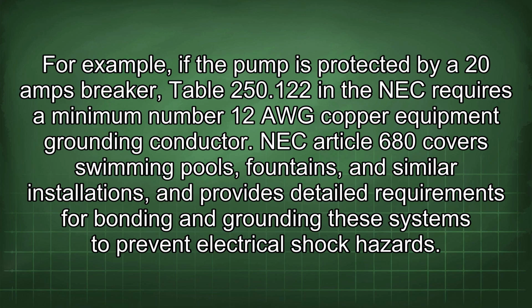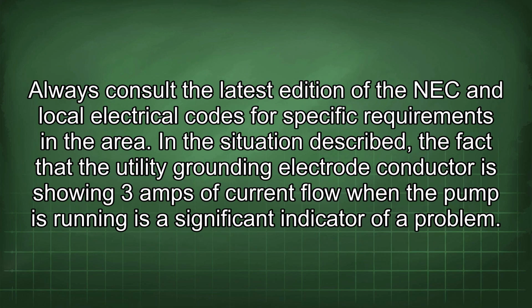NEC Article 680 covers swimming pools, fountains, and similar installations, and provides detailed requirements for bonding and grounding these systems to prevent electrical shock hazards. Always consult the latest edition of the NEC and local electrical codes for specific requirements in the area. In the situation described, the fact that the utility grounding electrode conductor is showing 3 amps of current flow when the pump is running is a significant indicator of a problem.